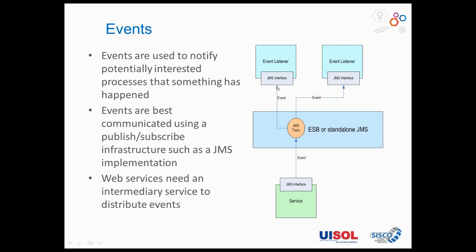The outage management system, when it hears a last gasp, it may then take on other actions and do other things across the bus, such as a ping to verify or to send some sort of other outage report out. So that's what's going to happen if you're just using it for events. And this is really a publish and subscribe type event, because if you'll notice, it's going out to multiple subscribers of that event.